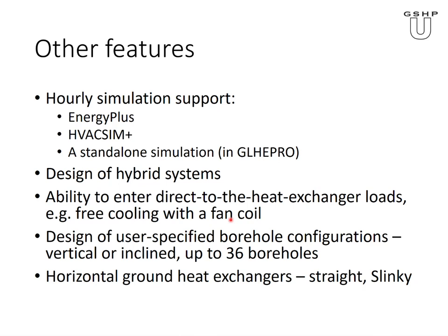I showed you a library. I also told you that you can take rectangular cases up to 10 by 99 boreholes. We also have another feature for irregular borehole configurations. You can specify up to 36 boreholes, and you can specify the position of every single borehole. So if you have a banana-shaped field, you can specify that.